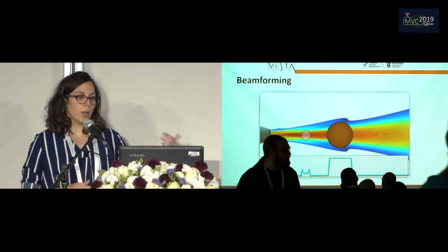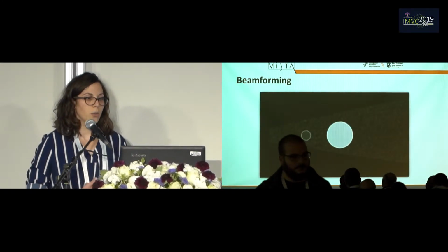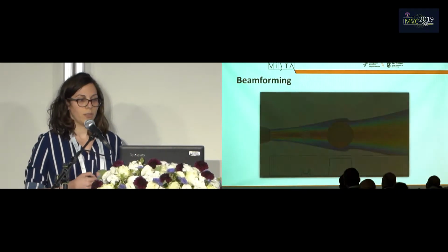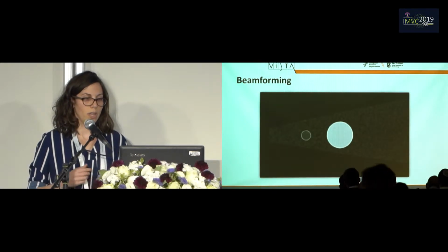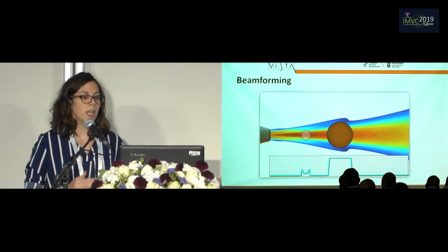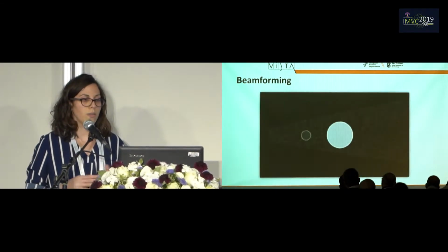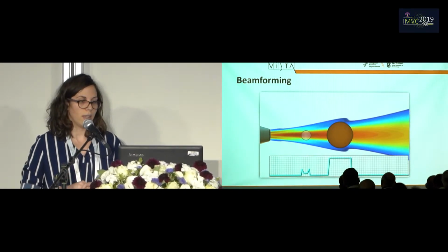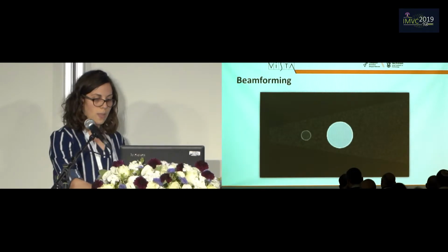We can also focus this acoustic beam in a process we call beamforming, in which we add phases to the signals coming from the elements of the transducer. This way we create constructive interference in the focus area, as you can see in the video, in the red area.